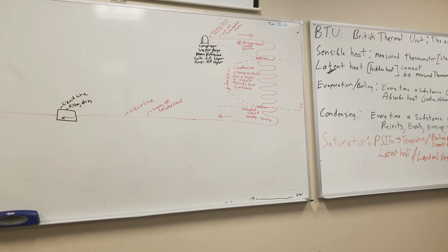What do you think that mixture is coming out of this metering device? Approximately 75% liquid, 25% flash gas. Heard of Flash Gordon? This is the flash gas. 25%, bam, immediately flashed into a vapor. Did it change state from a liquid to a vapor? Yes, immediately.